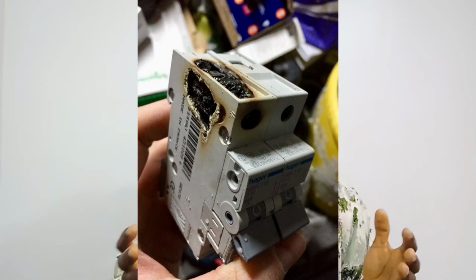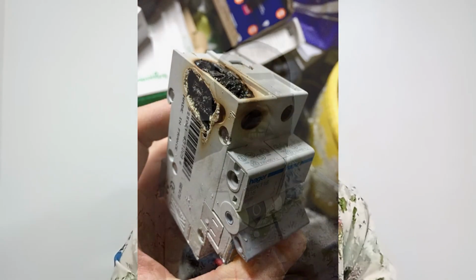And also, undersized circuit breakers, SPDs and fuses can cause fire outbreak in your solar system setup. Make sure that you use the right fuses and the right SPDs with the correct voltage and current rating for your installation to avoid fire outbreak.